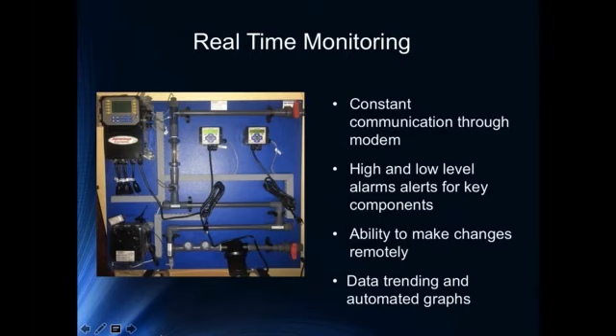And so we constantly know what's going on with the system. We know what the key parameters are, and we can set alarms so that if something goes out of range, it alerts us. If the conductivity in the system gets low, and it would get low if you're adding too much water because your makeup valve's stuck open, or your solenoid valve stuck open and you're dumping more water than you should, all of a sudden an email comes through to your operations staff, to our service team, says, hey, we've got low conductivity at XYZ Plastics. We pick up the phone, go out there real quick, check to see, sure enough, solenoid valve failed, replaced it, got it done.